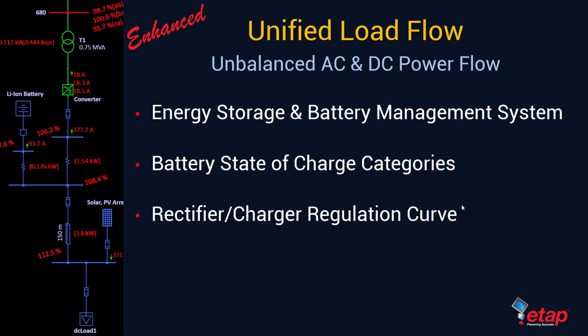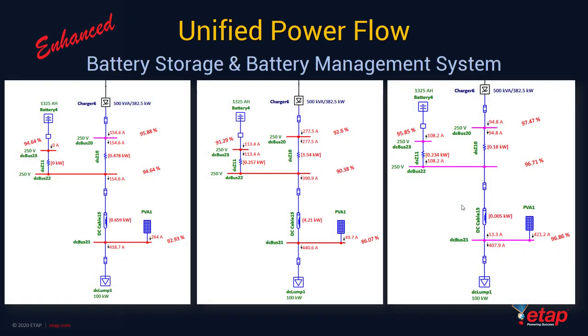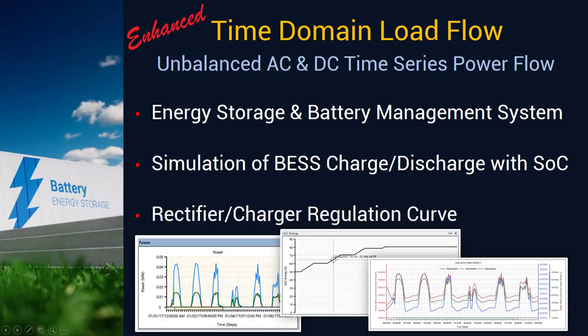DC short circuit has been enhanced to include contribution based on state of charge of the batteries. The unified load flow module includes unified unbalanced AC and DC power flow simulation, including energy storage and battery management system, battery state of charge categories, and rectifier or charger regulation curve. The rectifier or charger inside ETAP can be used for charging and discharging the battery, allowing bi-directional power flow. For unified power flow, you can simulate under-voltage conditions where the battery supplies supporting current and power into the network, or over-voltage conditions where the battery absorbs power away from the network.